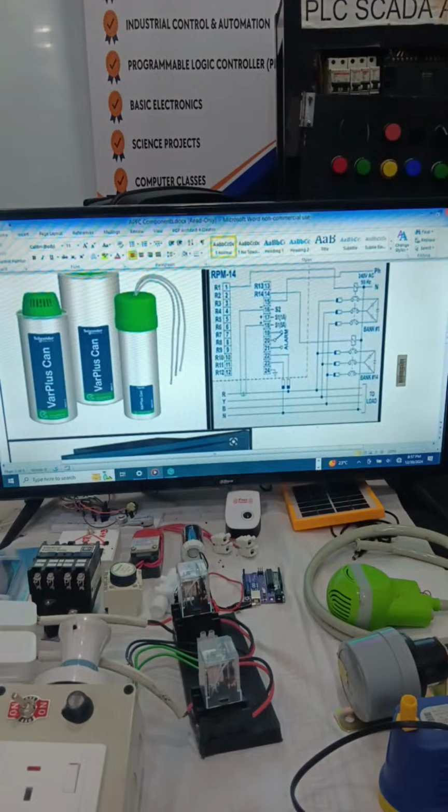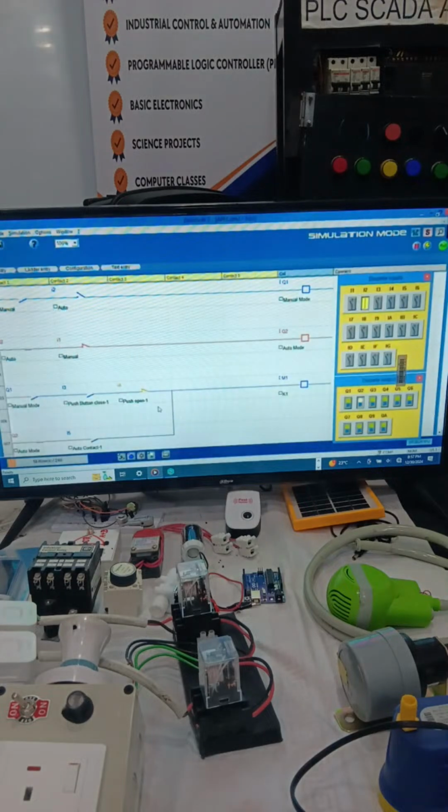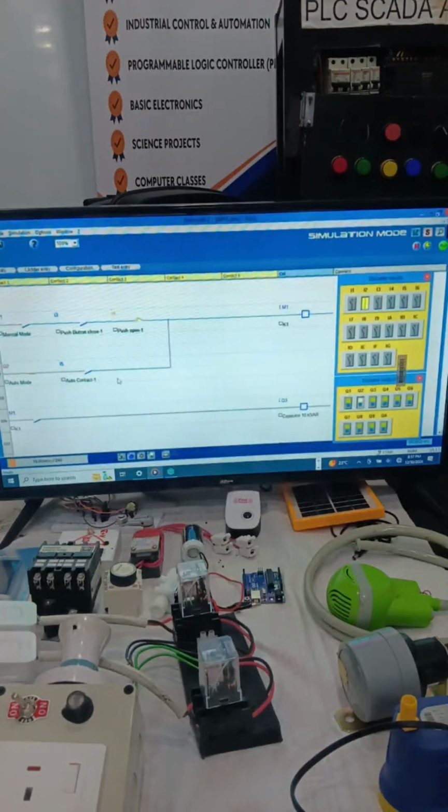So now in our system, we will consider this as auto contactor. Suppose the signal came to switch on one 10 kVA contactor, so this will close. The controller will give this. Now you see this 10 kVA capacitor is on. Now suppose the demand requires more, so an additional 15 kVA. So the second contactor will close from the controller. Now you see one 15 kVA capacitor is on. Now it is 25, 10 plus 15.